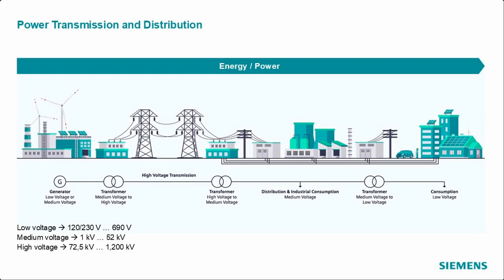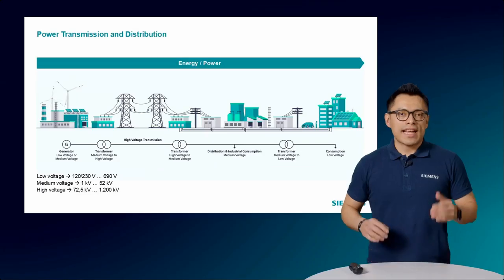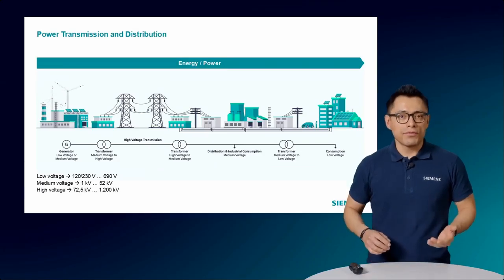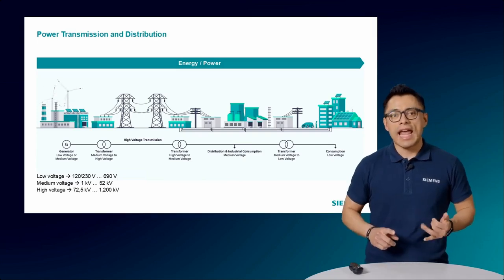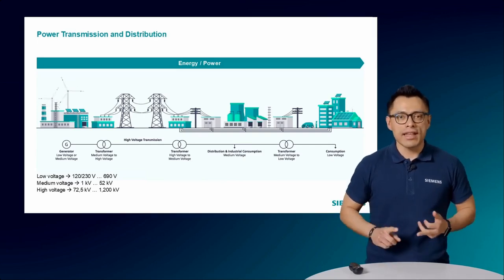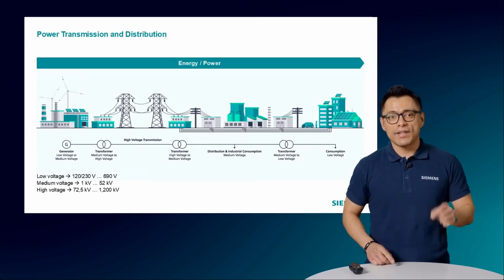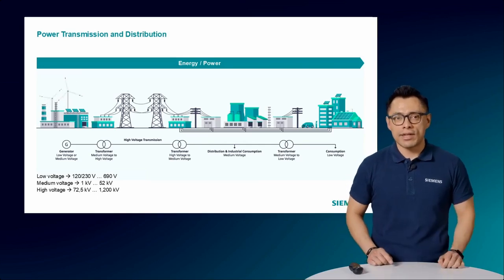Generally, the voltage level classifications are low voltage, using voltages from 120 volts up to 690 volts, medium voltage, using voltages from 1 kilovolt up to 52 kilovolts, and high voltage, using voltages from 72.5 kilovolts up to more than 1000 kilovolts. The exact ranges depend on the source of information, such as international standards, academic articles, or industrial sector guidelines. Nevertheless, this classification is widely accepted and accurate.